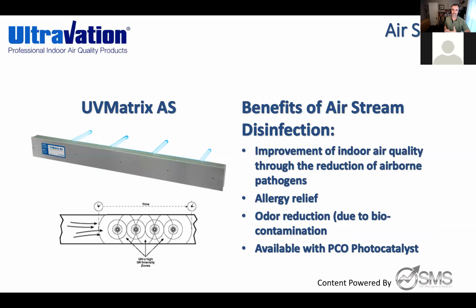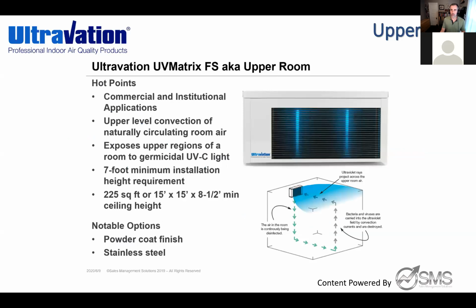And then depending on the velocity and amount of air being pumped through there, we've seen applications where we might have to put, maybe you don't have to go double across, but you might see 2 of these racks in a row to give you more of that time and intensity depending on the disinfection rate the customer wants. If people just want a standard disinfection rate like 60 to 70% because they had nothing before, you might only have one of these. But if they want a maximum 90% disinfection rate and they're trying to kill everything possible, you might see more of these quoted on a job. So I just like to clarify that because it might not always be just one.